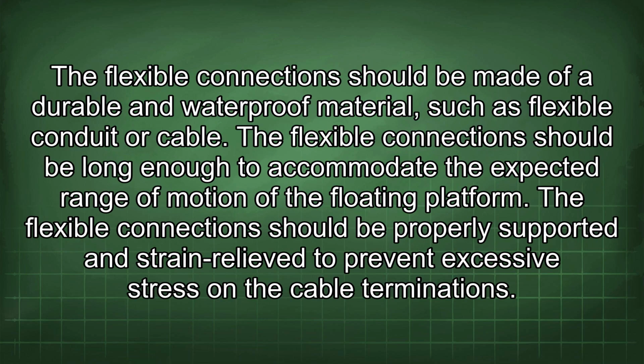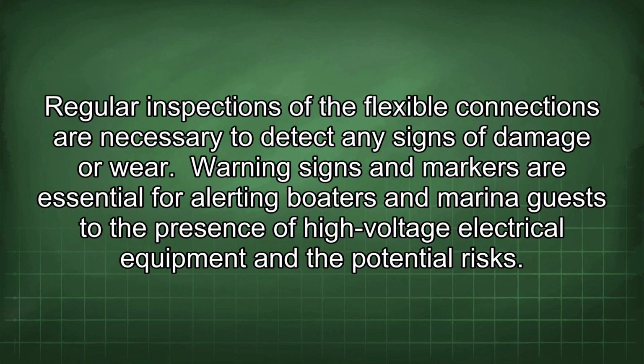The flexible connections should be made of a durable and waterproof material such as flexible conduit or cable. The flexible connections should be long enough to accommodate the expected range of motion of the floating platform. The flexible connection should be properly supported and strain relieved to prevent excessive stress on the cable terminations. Regular inspections of the flexible connections are necessary to detect any signs of damage or wear.